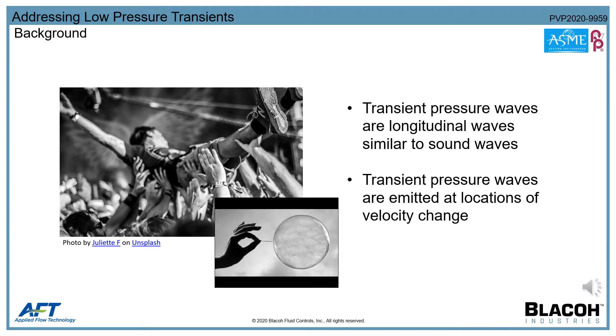This type of wave is a compression type wave, or more technically known as a longitudinal wave. In fluid piping systems, the cause of these pressure waves is due simply to a change in velocity — for example, by closing a valve or starting a pump. Low pressure transients commonly occur at the discharge of a pump during a shutdown or unplanned pump trip. This same type of transient is also initiated on the discharge side of a closing valve, and can be a secondary event after a high pressure transient occurs.